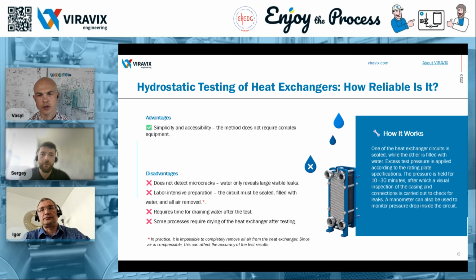Sergey, could you share your experience as well? How do hydraulic tests compare to other methods you've worked with? Yes, absolutely. I agree with Igor. Because with this test, only clear and visible water leaks can be detected. For example, if water droplets actually appear on the outside like this, then you can clearly see them. But when it comes to the size of microcracks, that's a different story, especially when using a gas test. For instance, I've spoken with maintenance staff who said there was no water leakage here. But when we ran a gas test, it clearly detected a leak. That's why it becomes evident that hydraulic tests simply don't reveal microcracks. They're just not sensitive enough to pick up such small-scale damage.